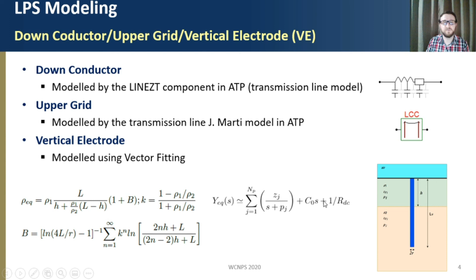For modeling the down conductors, we use the component LINEZT in ATP software. The upper grid is modeled by the transmission line JMarti model, and for the vertical electrode, when considering stratified soil, we use these formulas to compute the equivalent soil resistivity, then compute the admittance and apply the vector fitting technique, from which a representative circuit is obtained.